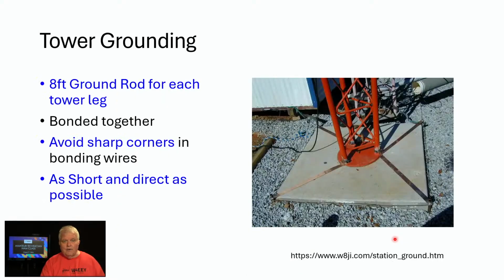And if you're going to put up a tower, we need to worry about tower grounding because lightning might not hit the antenna, but it might hit your tower. The rule is to have an 8-foot ground rod for each tower leg. And so in this case, we've got 3 tower legs. We've got 4 ground rods actually. One over here, there's a ground rod there. One back here, there's a ground rod there. One over here, there's a ground rod, and another one over here. And they're all bonded together with mechanical clamps and wire here to keep them all at the same potential. Again, we want to avoid sharp corners, and we want to make them as short and direct as possible.